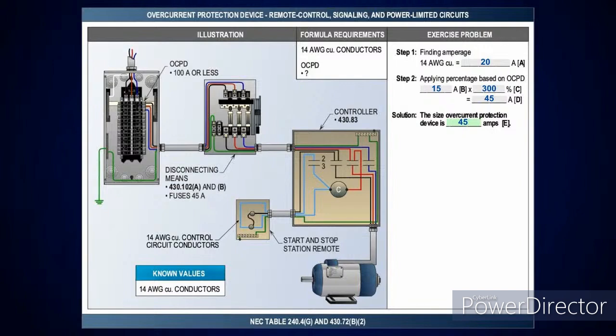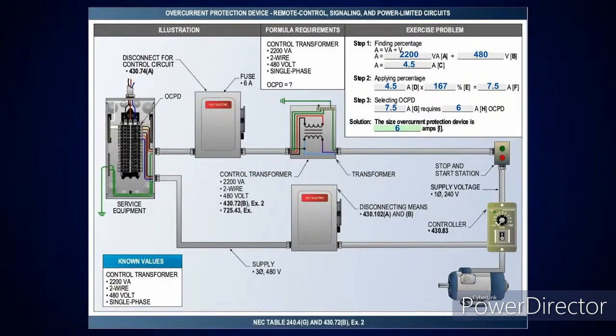All right. Now, this is where you're going to see the control conductors running remote from the enclosure, going over to a start and stop station that's remote. If you look at this, you're going to look at note 3 because they're remote. It tells you to use the 60 degree C conductors, but it's table 310.16 because those were run in what? A conduit. So if you look at table 310.16 for your 60 degree C column, it's going to tell you it's good for 20 amps. You take that and base it on the overcurrent protection device. So I've got a 15 amp overcurrent device, and you take that at 300%, which gives you 45 amps. And if I look at column C, conductors that extend beyond the enclosure, and pick up number 14, come across, what does it say? 45 amps. Right. Isn't that amazing? So that proves everything we were showing there.